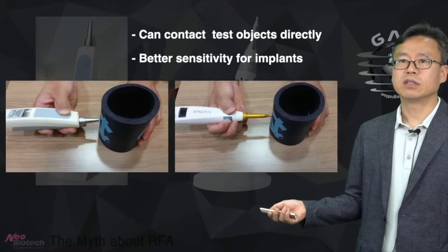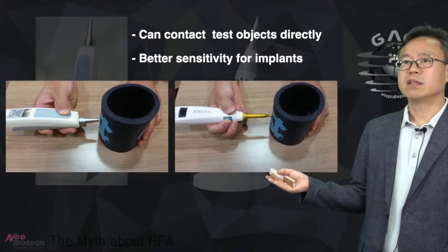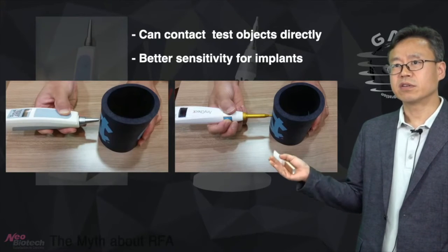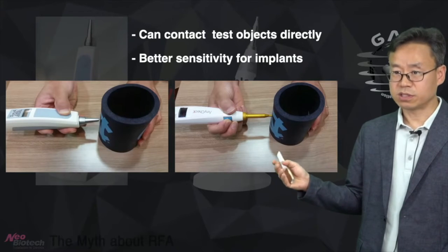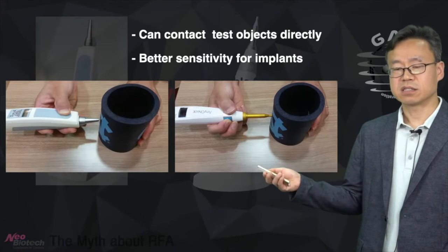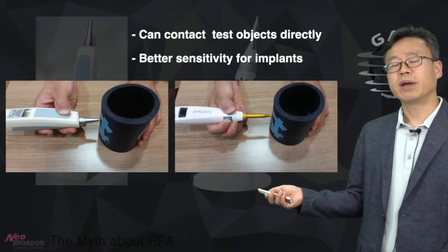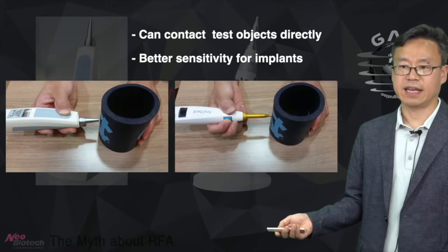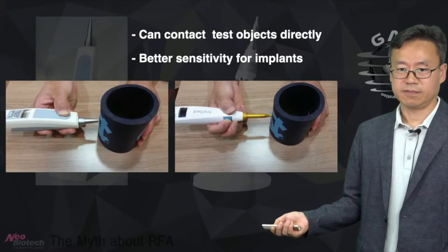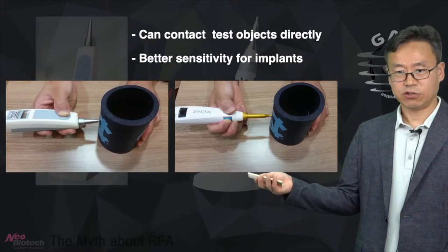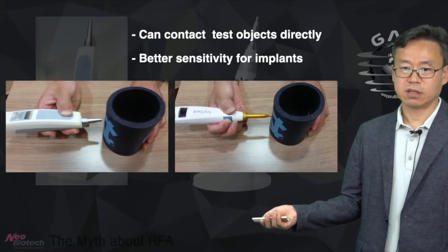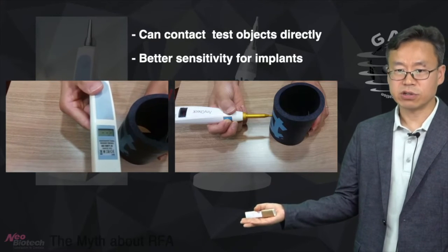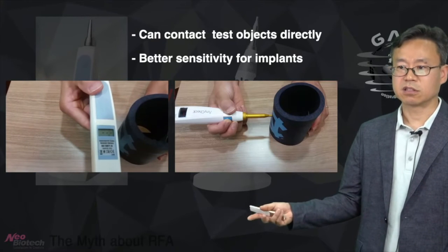And also, when the object is highly mobile or soft, like this rubber cup, the Periotest cannot measure the contact time, whereas AnyCheck can. Let's see. See, you hear a high-pitched sound because it's not really measuring it.